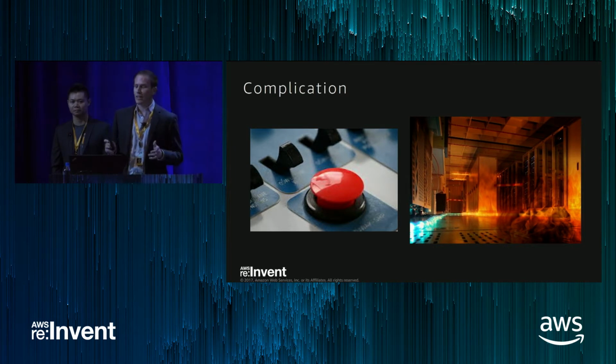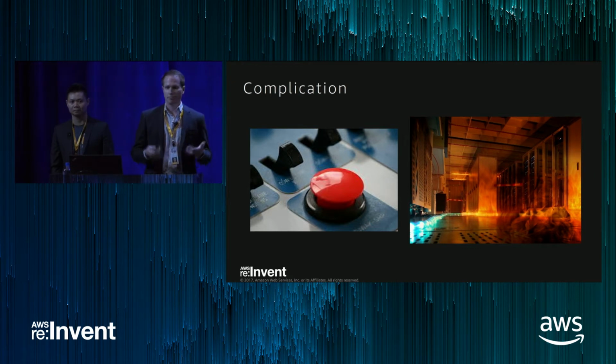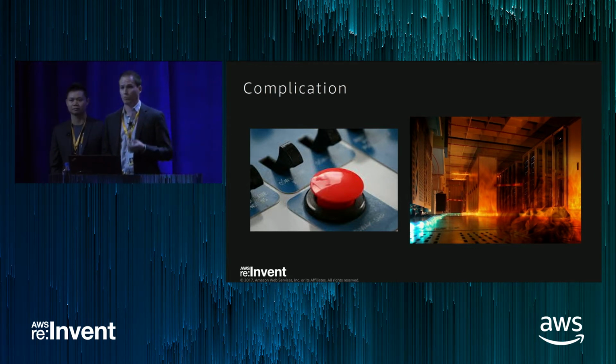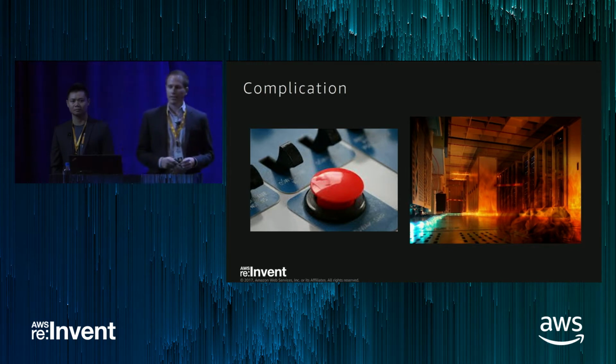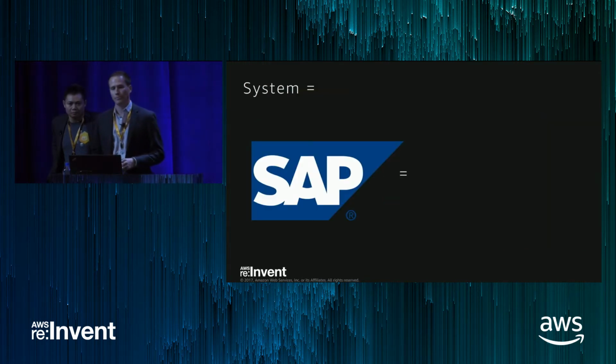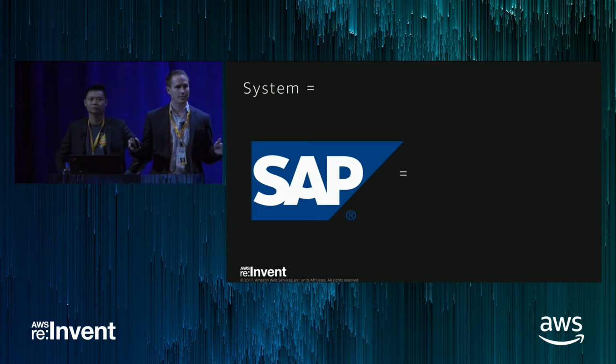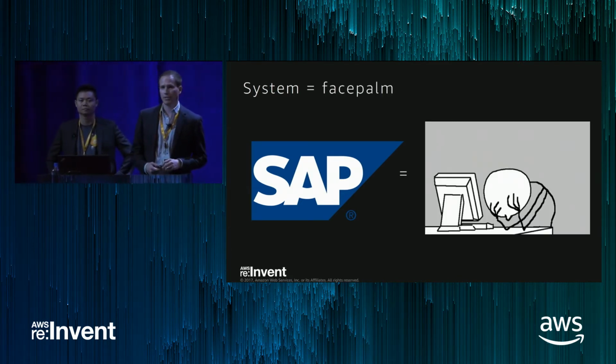Mind you, there isn't actually a real fire taking place here, but the system thinks there is because the alarms are tripped. So it releases fire suppression gas, which then triggers the air conditioning to turn off so you don't feed those fake flames with additional oxygen. And it turns out that those servers actually need that air conditioning to work properly. So if you've been paying attention to the news, this exact scenario happened, and the result was a 7-hour downtime.